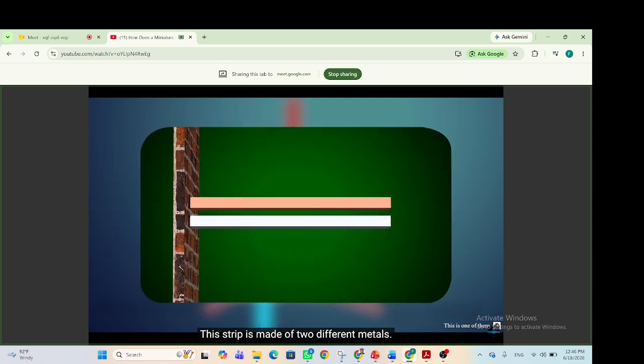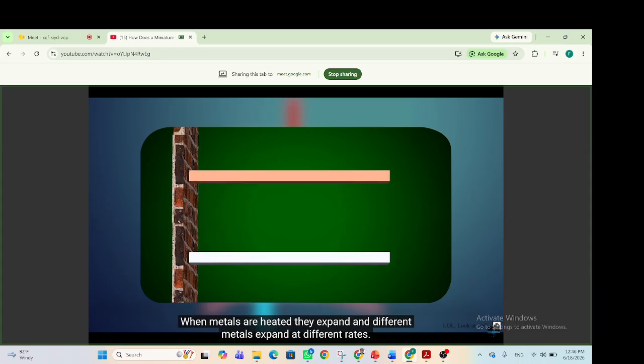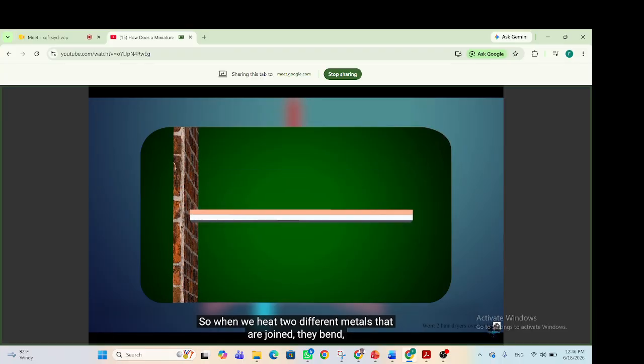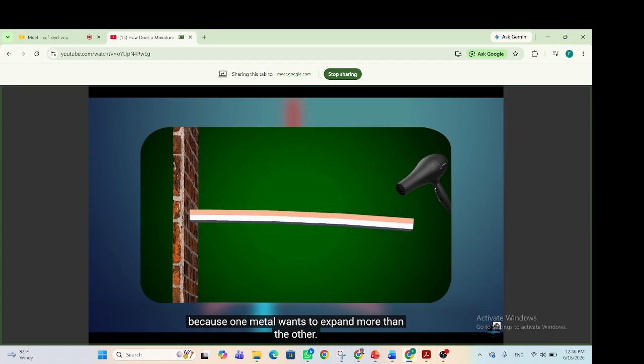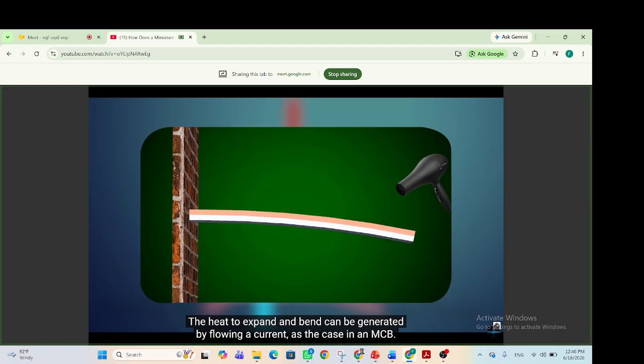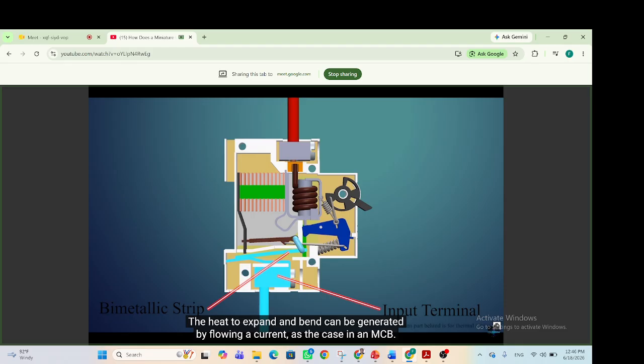This strip is made of two different metals. When metals are heated they expand, and different metals expand at different rates. So when we heat two different metals that are joined, they bend, because one metal wants to expand more than the other. The heat to expand and bend can be generated by flowing a current, as is the case in an MCB.